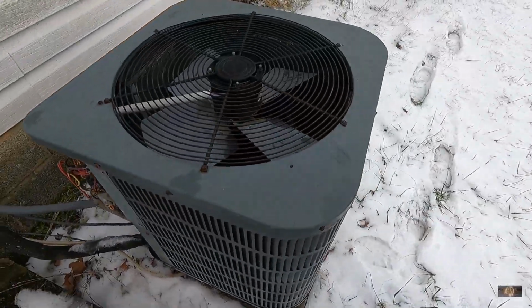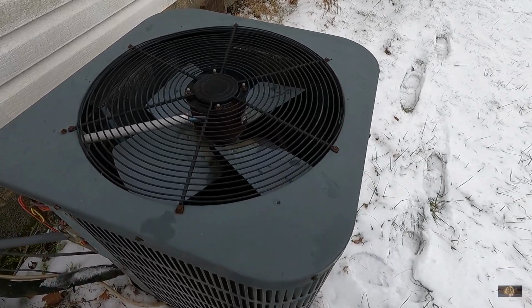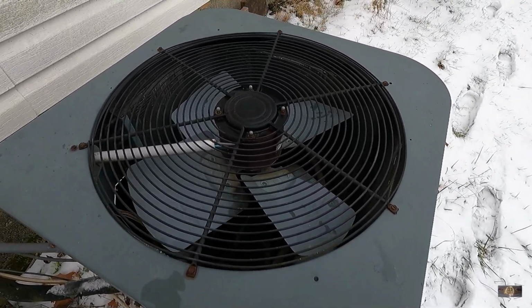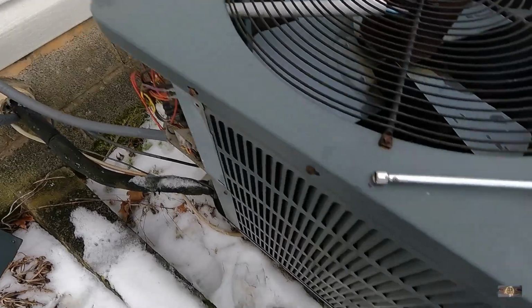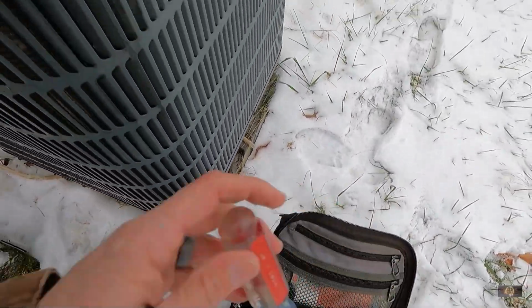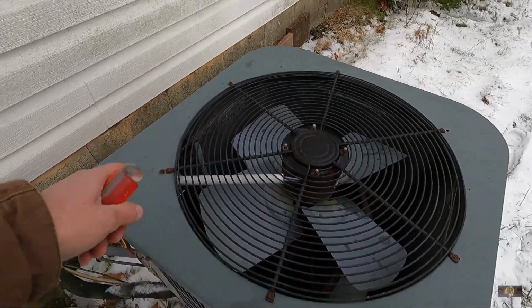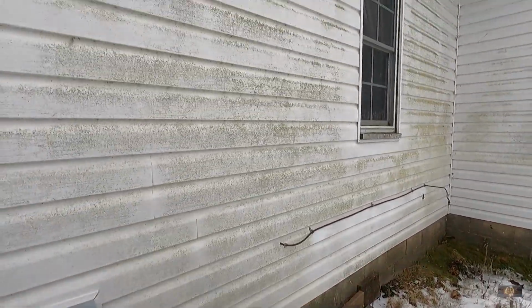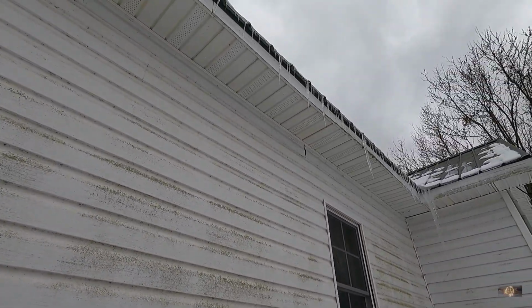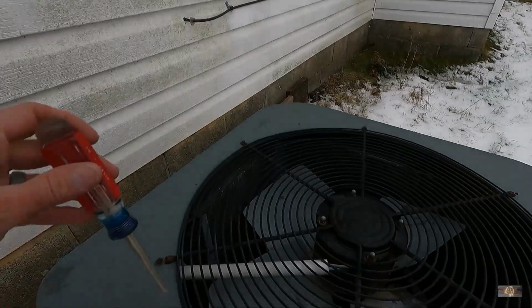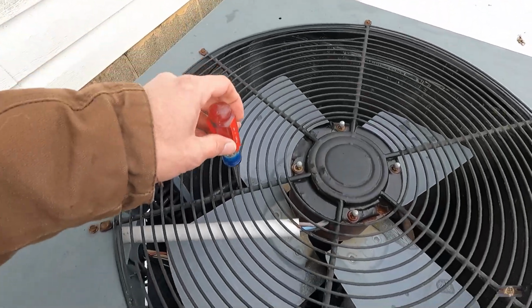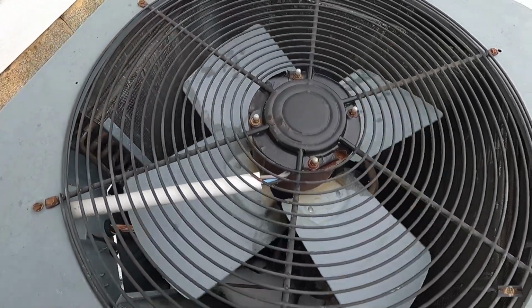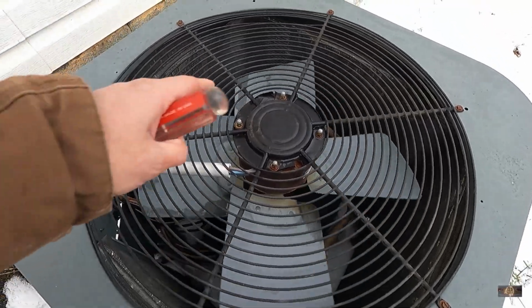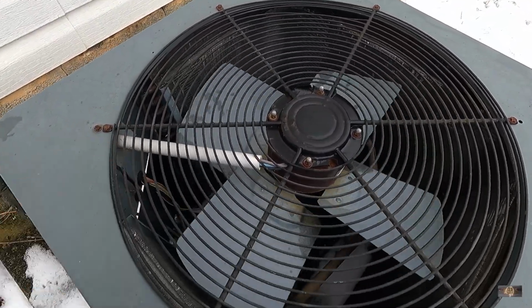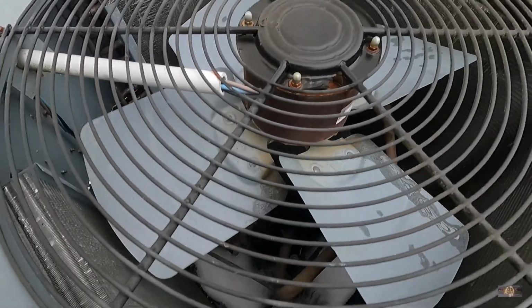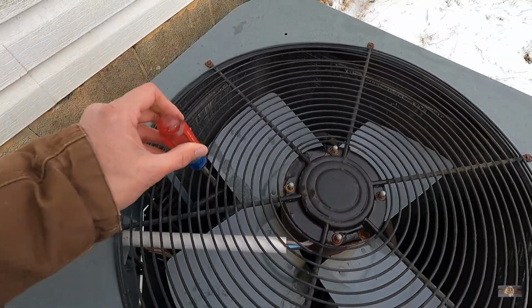Okay, so here's our outdoor unit. I'm going to spin the motor and see if I can see anything. I went ahead and took the panel off here. It's an old R22 Goodman heat pump. I did notice something right away. I'm getting dripped on right here. If you look up, there are no gutters on this house. Icicles are forming there, so I wonder if maybe when it was snowing, we had some ice accumulating in here, keeping this fan from running. Who knows? It appears to be spinning free.